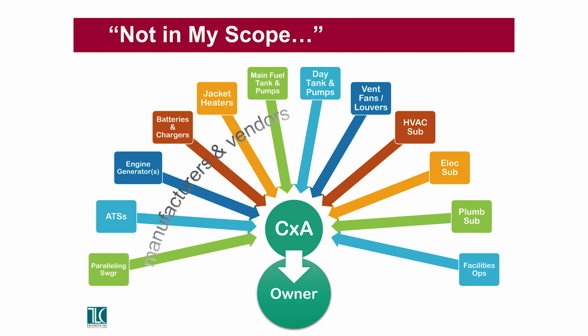That and superheroes. But the biggest thing I hear most often during construction sites and acceptance testing is, 'that's not in my scope.' Because just like in HVAC systems, there's lots of different pieces being provided by lots of different people. So you've got the generator vendor, the paralleling switchgear manufacturer, and transfer switches coming from a different vendor. Fuel system - the main tank's provided by one person, the day tanks might be provided by the generator people, or they might be provided by somebody else.